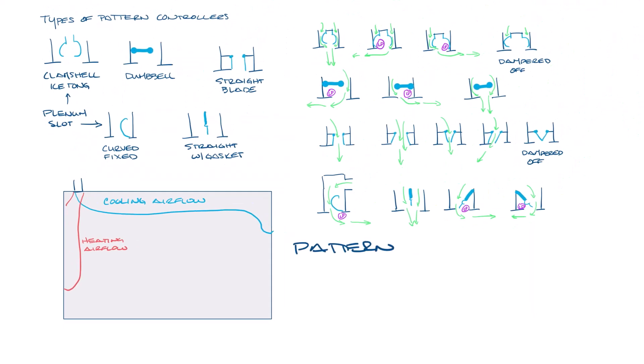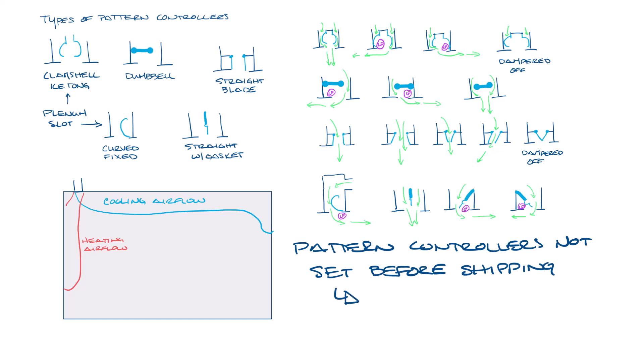Linear diffuser pattern controllers are not usually in the correct position when they ship. So hopefully now you can see where the low pressure areas are in the linear diffuser and how you can get the airflow to go where you need it to go, so you can adjust them for your specific application.